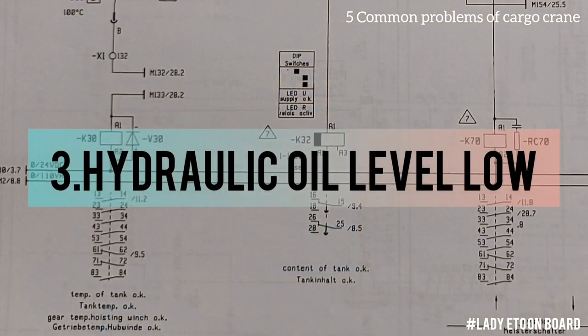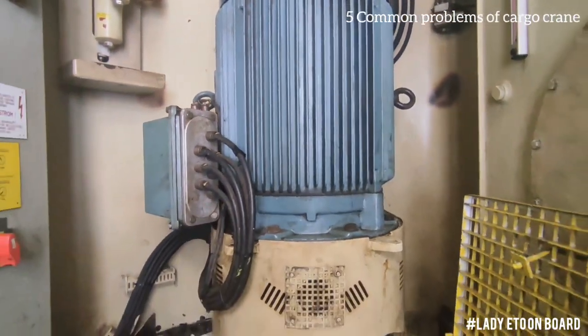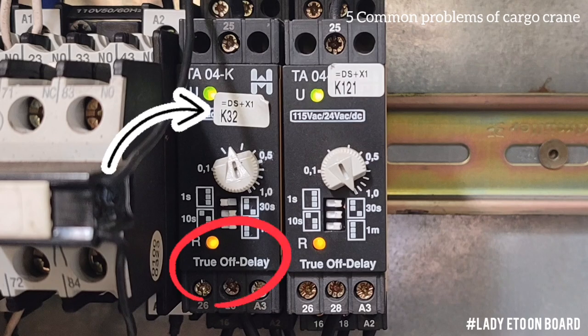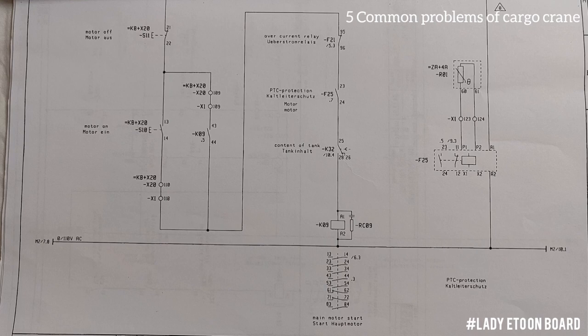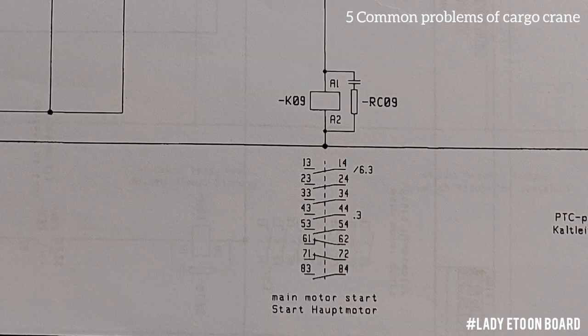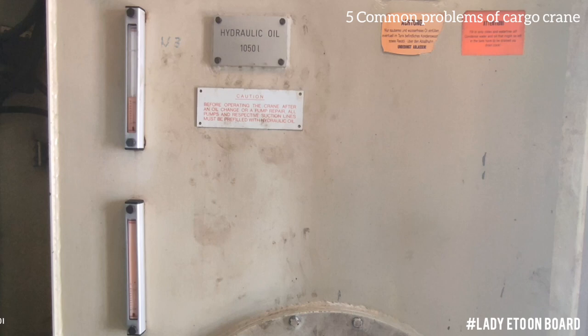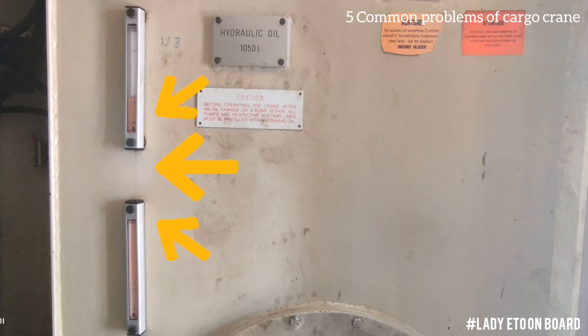Number 3 is hydraulic oil level low. In this case the electrical motor will trip. If low oil level is detected by the level switch, it will de-energize K32 and trigger an off-delay timer. Once the set time is over, the contact of K32 will open, K09 will be de-energized, and the motor will stop, because K09 is the auxiliary coil for the motor. You can also check the oil level on the level indicator. By pressing the on button you can restart the motor.